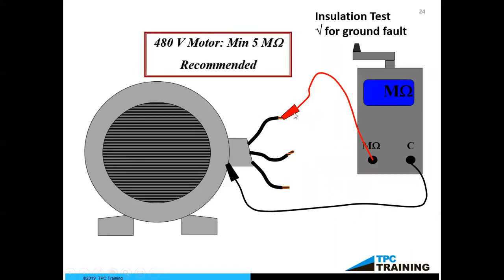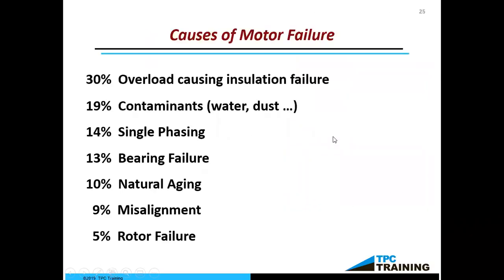So once I did T1, I would move my red lead to T2. Then I would move my red lead to T3, check all 3 windings, and make sure that that insulation is above 5 megohms. And hopefully it's up near open line, which is the best that we could possibly have.